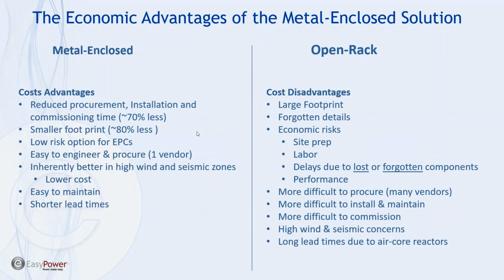So let's look at metal-enclosed versus open rack, some cost advantages. For a metal-enclosed system, there is reduced procurement cost. What does that mean? When you go to a supplier for metal-enclosed capacitor banks or harmonic filter banks, you're going to one supplier. That supplier will then package the equipment. They do all the engineering work, all the assembly work, and all the purchasing work, and therefore on the procurement side, there's just one item being purchased.